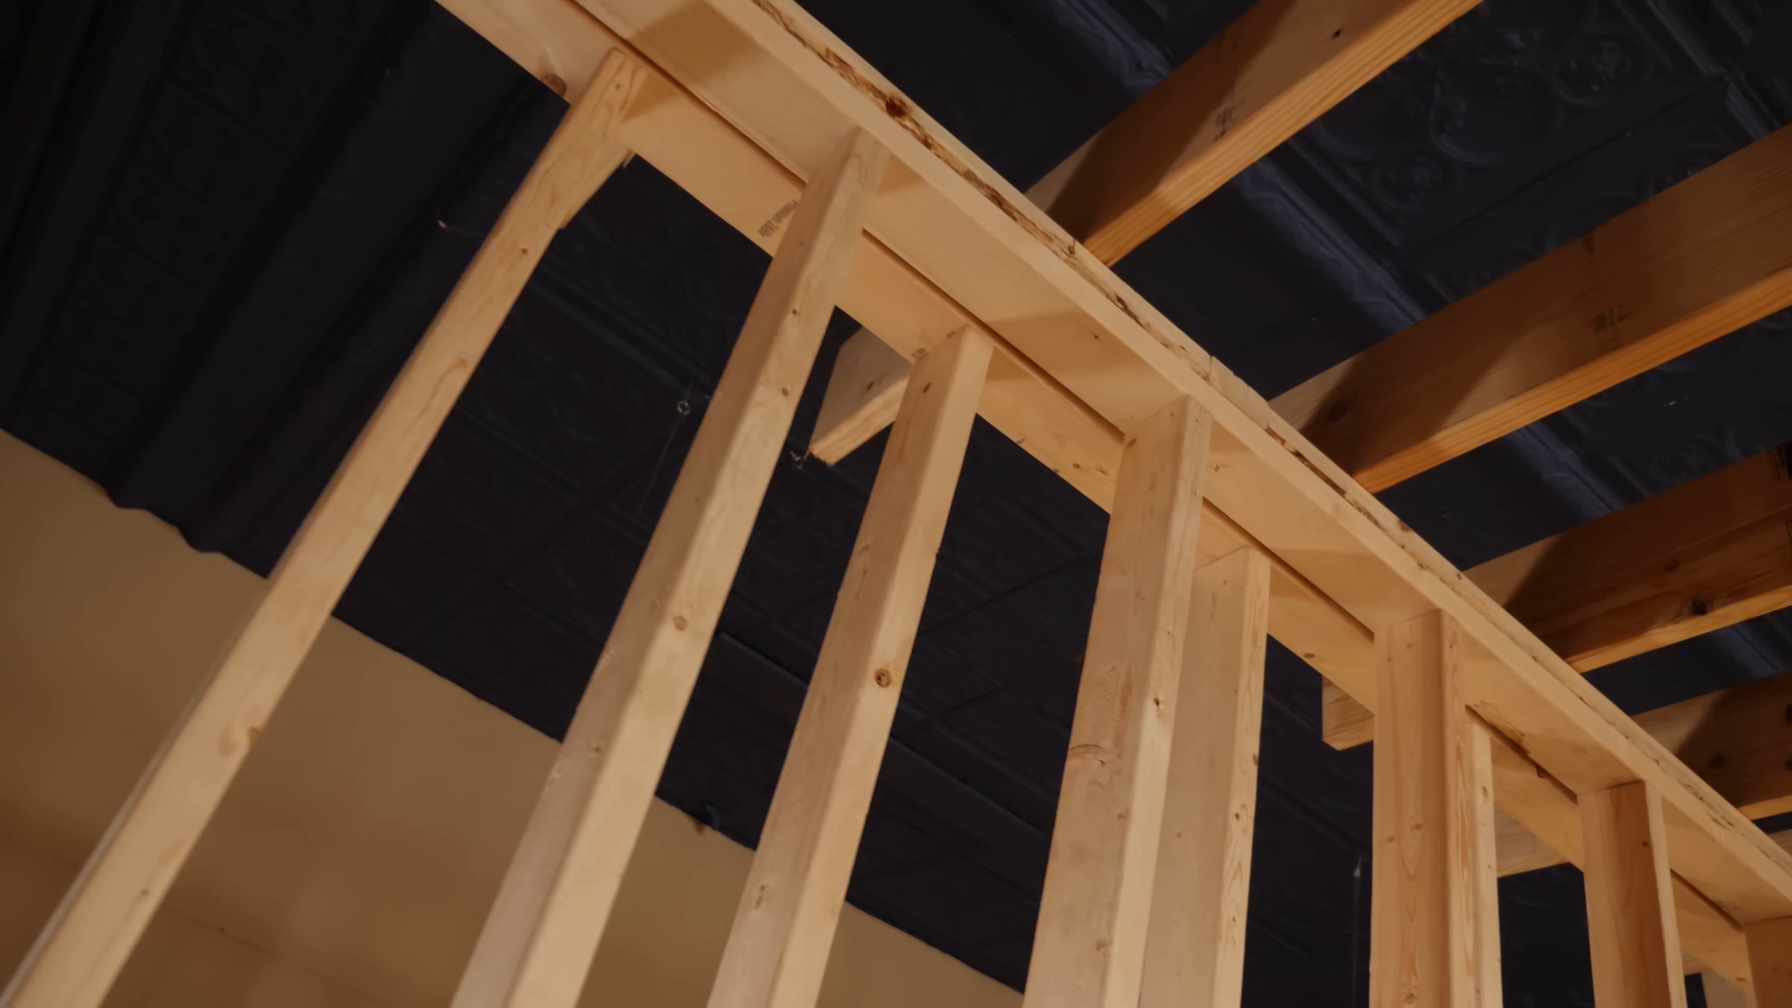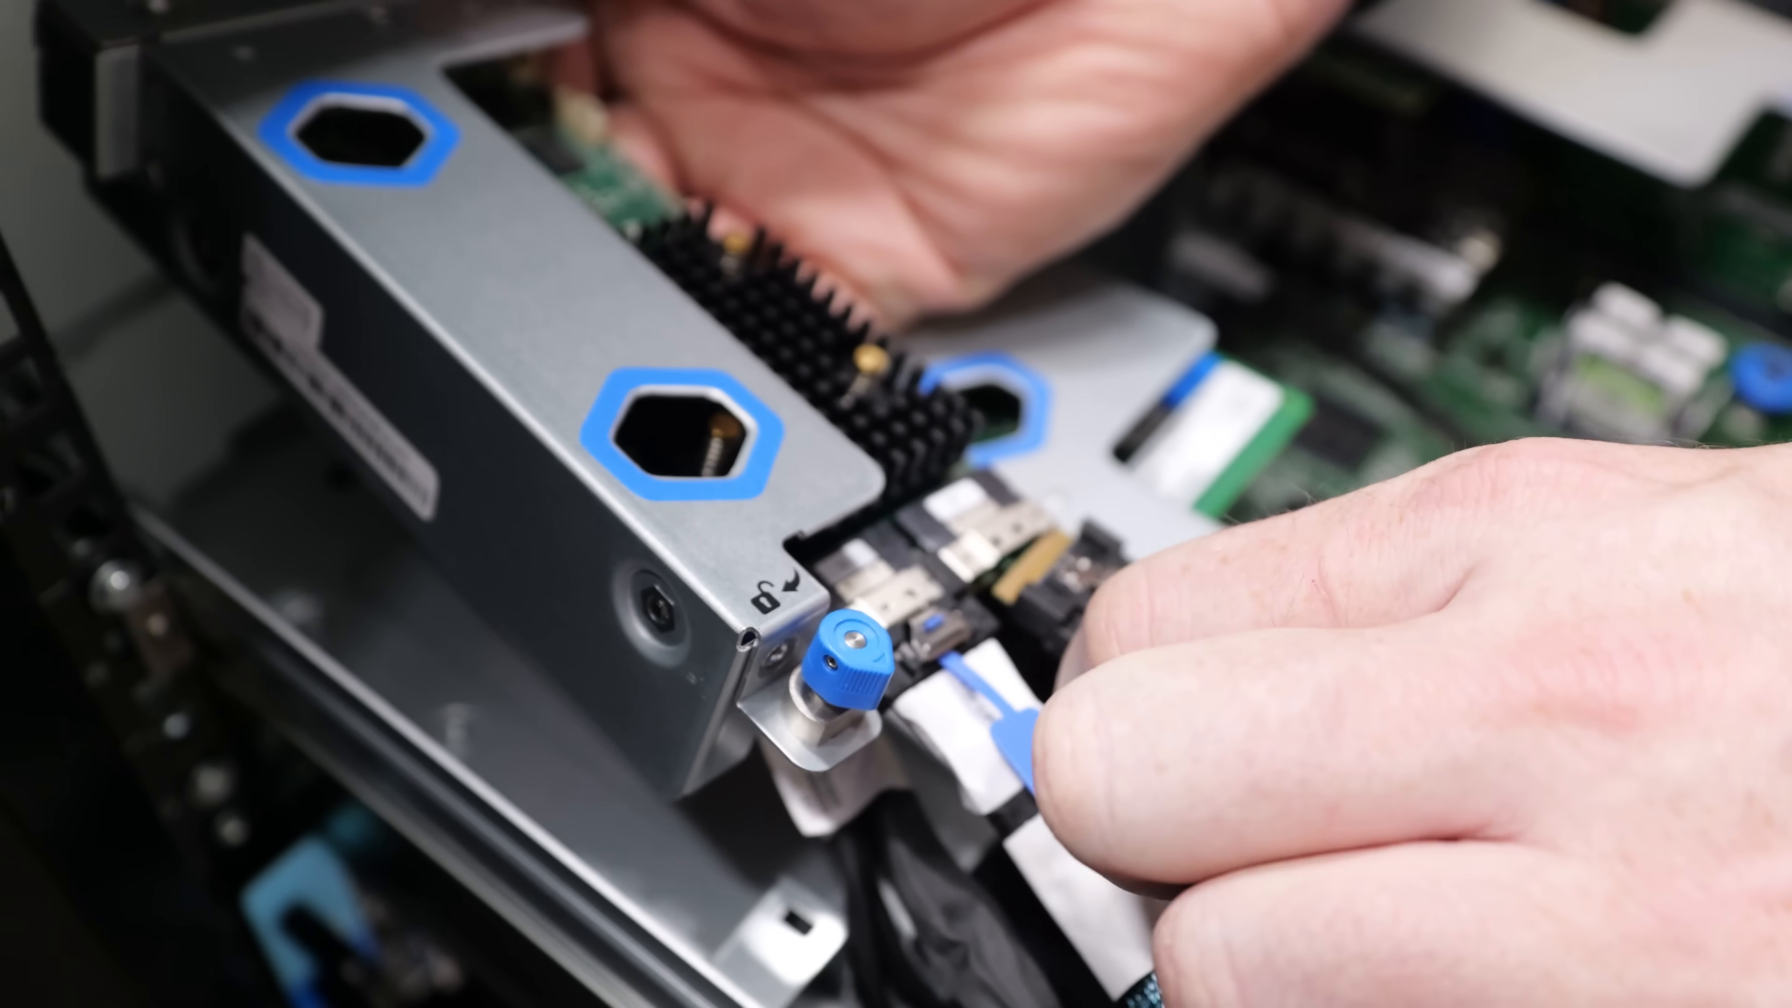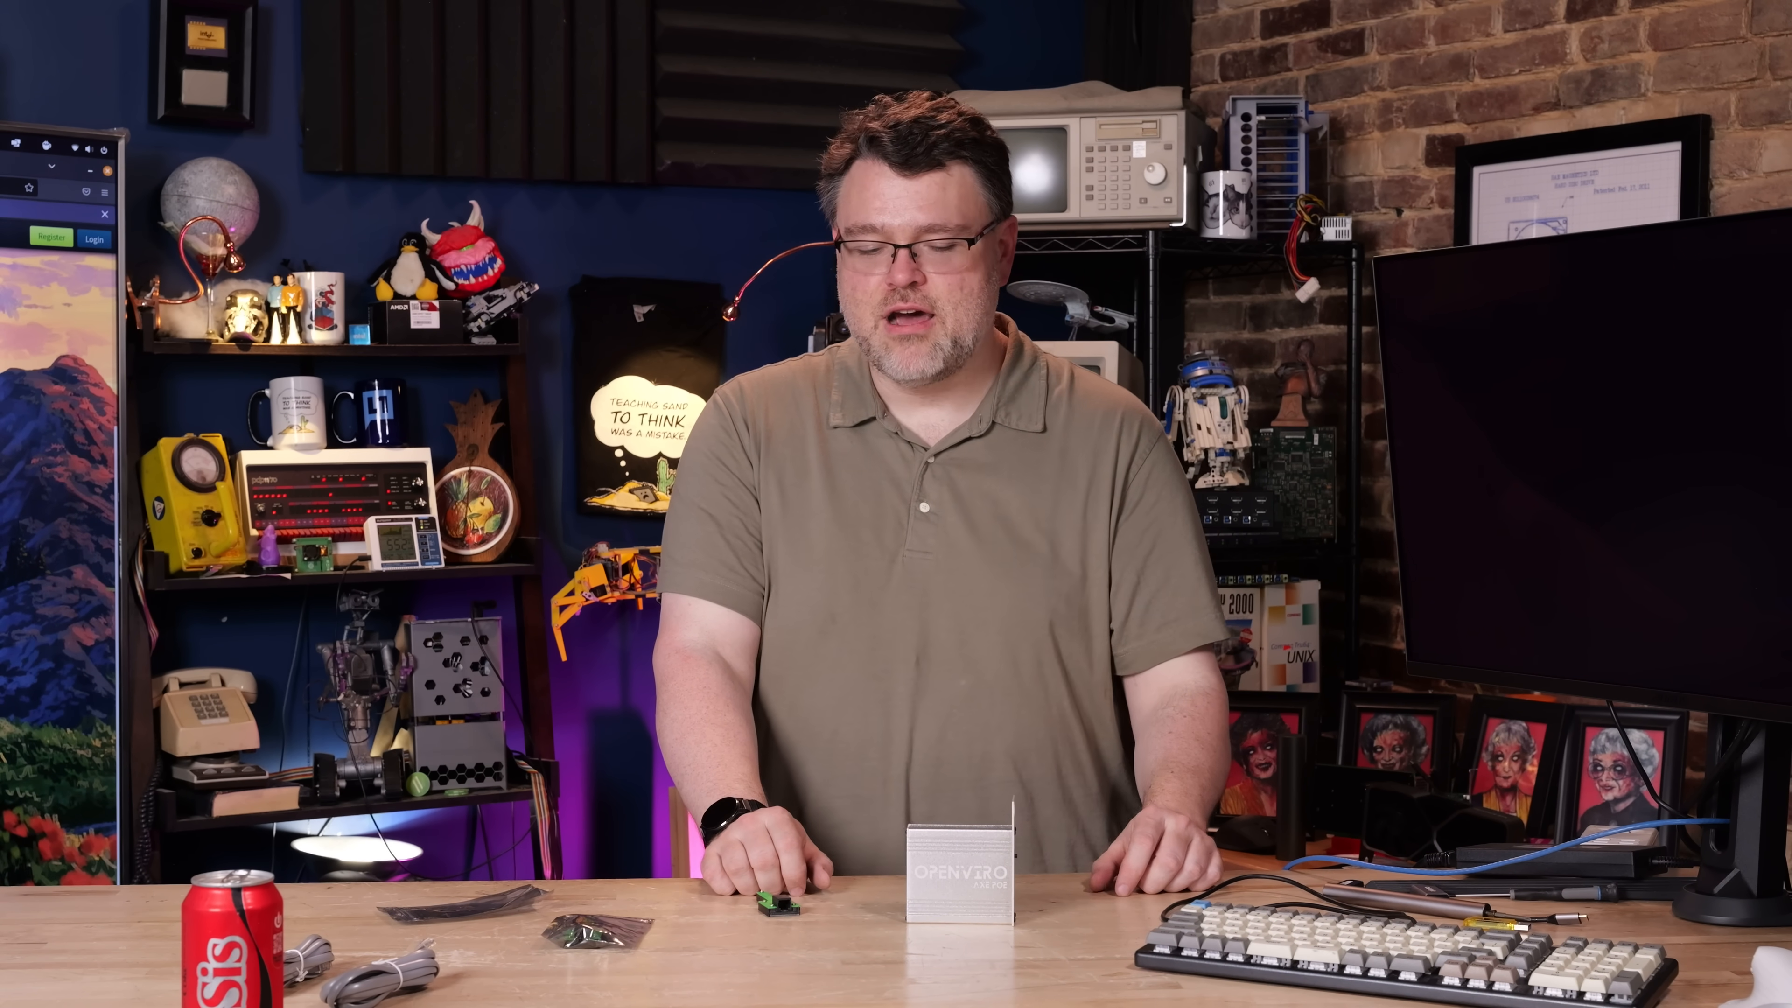The other aspect of this is actually using this for its intended purpose, monitoring a server closet. And because we've been getting more servers and doing more server videos and more test projects and working with folks on the forum for their various projects and just chewing up all kinds of electricity, the act of cooling in my server closet has been struggling a little bit. Even though it's more than five tons of cooling for a small little room, it's not quite enough. At that point, it makes more sense to throw a heat exchanger at it as opposed to a refrigeration system. Most of the time you can dump a lot of the heat outside and then use your refrigeration system to make up the delta, not just to fight wattage with wattage.